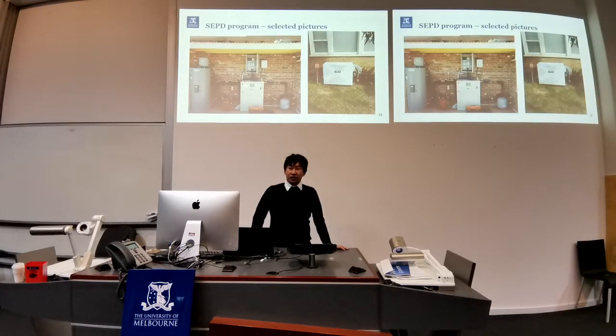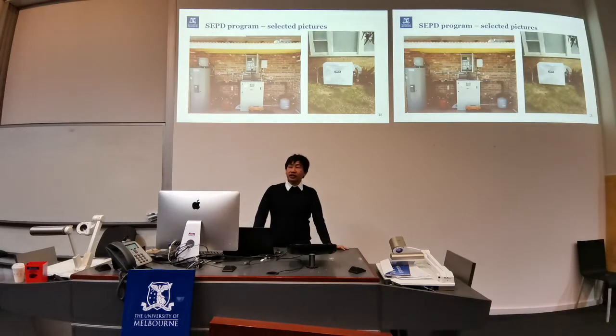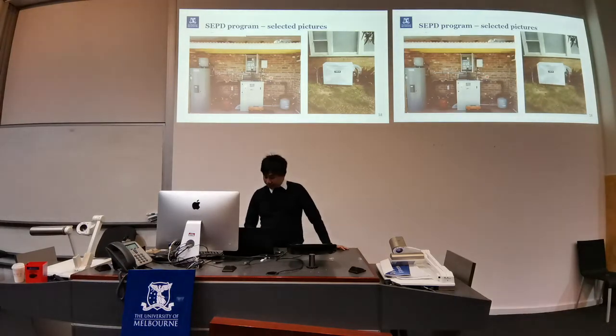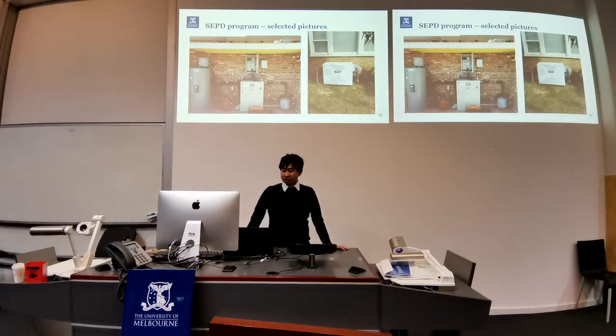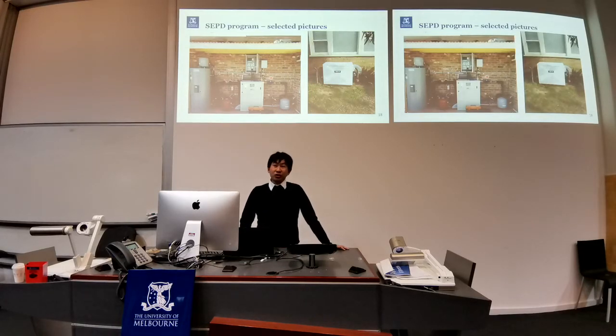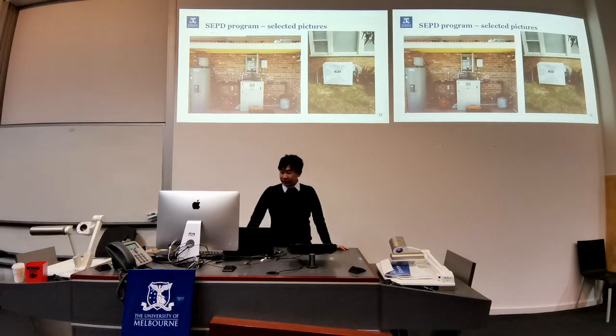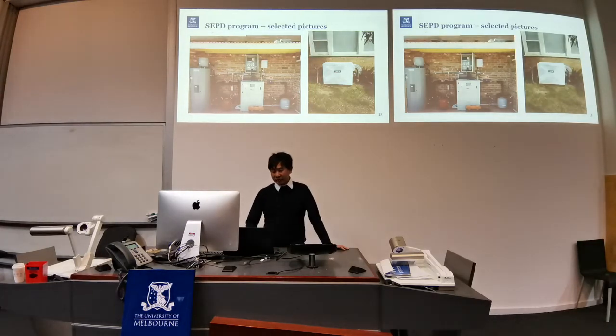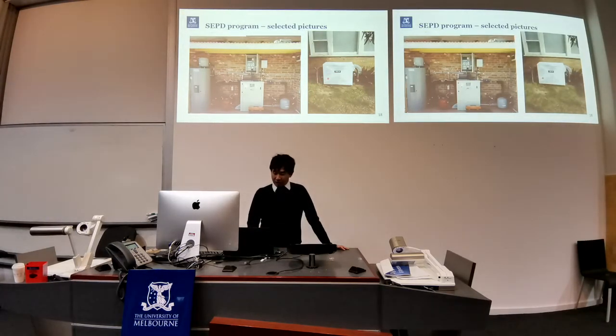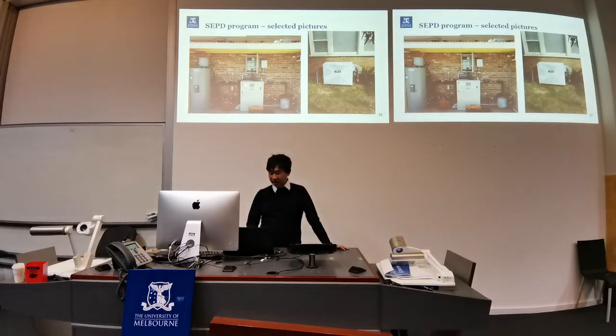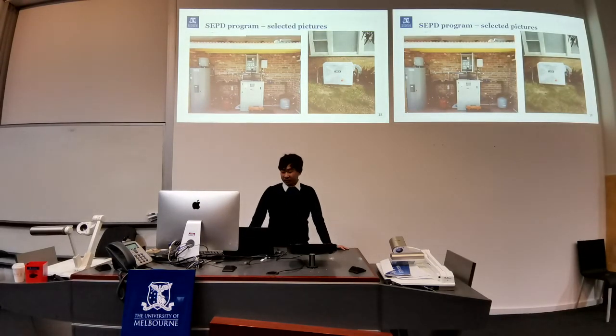We also used different ground source heat pumps. The one on the left is one that is available to purchase off the shelf. However, they are rarely sold in Australia and need to be imported from overseas. The whole process from ordering, manufacturing, testing, and delivery can take up to 3 months, which is no good for your project. For this reason, we also trialed some locally made heat pumps, such as the one on the right. This one is designed so that all the required components, such as the circulation pump, tank, and so on, are installed inside the heat pump itself, so it's very compact.